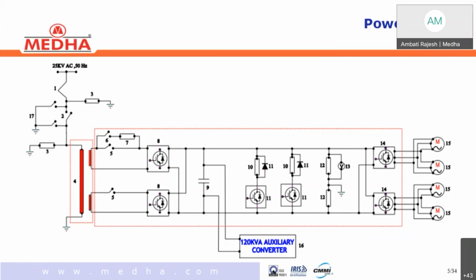At any time, either motoring or braking, whenever the DC link reaches the set value of 2100 volts, these brake chopper circuits come into picture and shave off the over and above voltages. Further, there is an earth leakage detection circuit, ELD. In the power circuit, whether in the DC link positive side or negative side, the traction transformer secondary side or the traction motor side, anywhere in the power scheme, if the power circuit is touching the body and leakage current is flowing, that leakage current will flow through this earth leakage detection mechanism. Whenever the leakage value reaches the set value, the system cuts off the traction with an appropriate fault message. So one basic unit gets disconnected from the overall rake power. This is about earth leakage detection, the power circuit ground detection point.